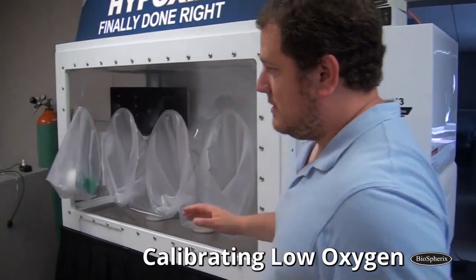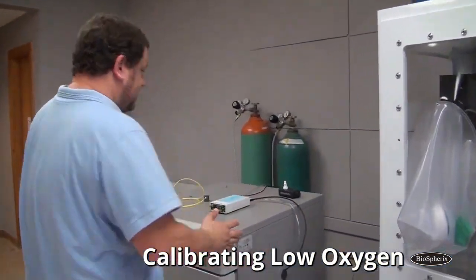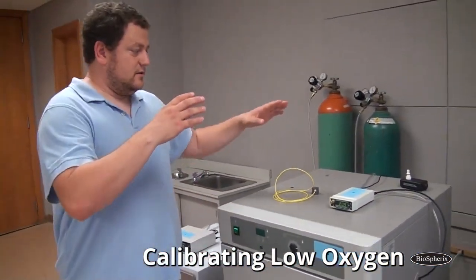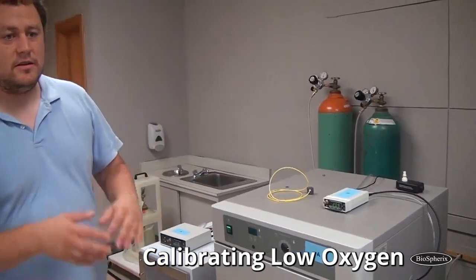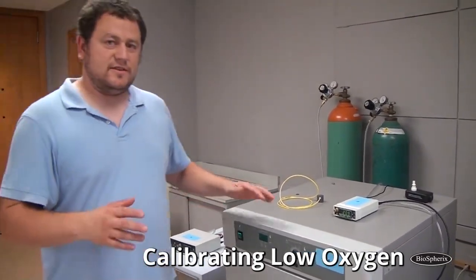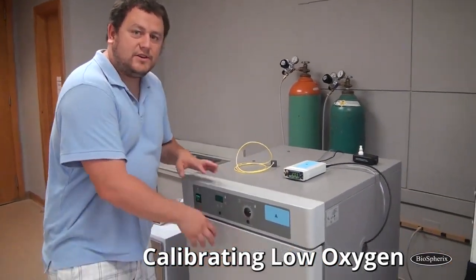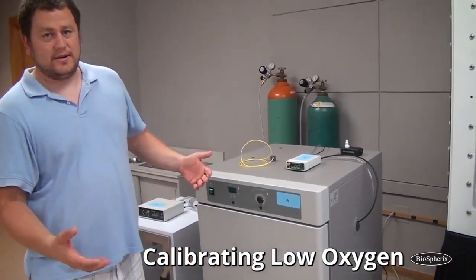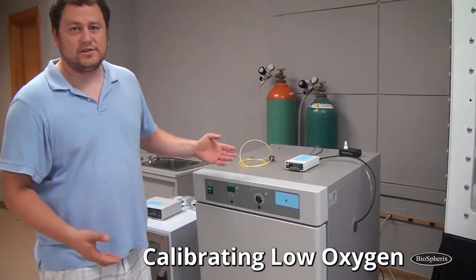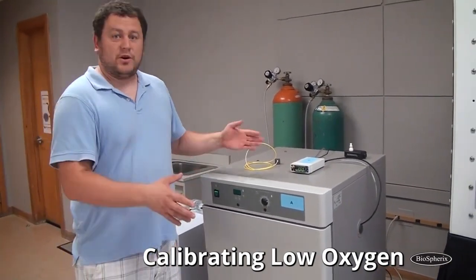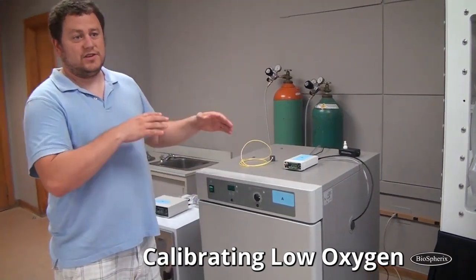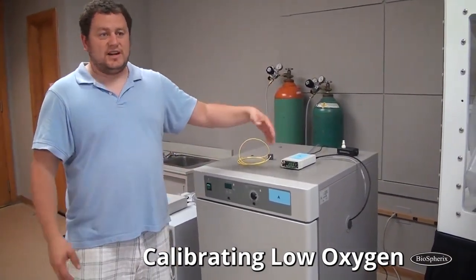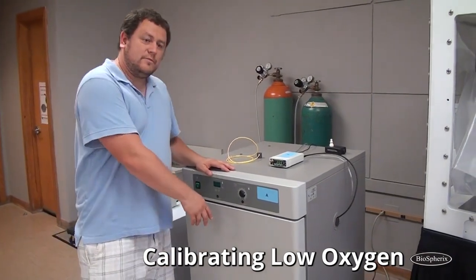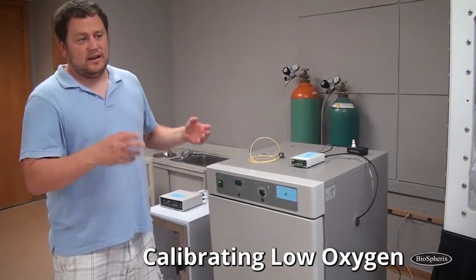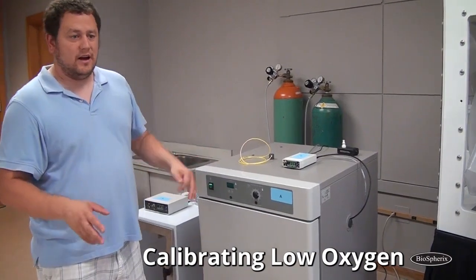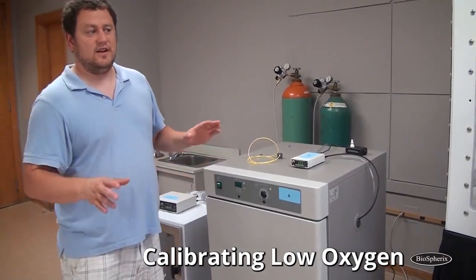The one little bit of difference if you're running an incubator setup is that the sensors do have a feel for the temperature. So if you're in a warm incubator, you don't want to take a half an hour doing your calibration. If you do it exactly like we just did, a couple minutes, it's perfect, it's fine, it's back in the temperature, your calibration's accurate. If you let that sensor sit out in room air after having it in warm for half an hour, the calibration is not going to be quite as accurate. You'll still be okay, but it does have an effect.